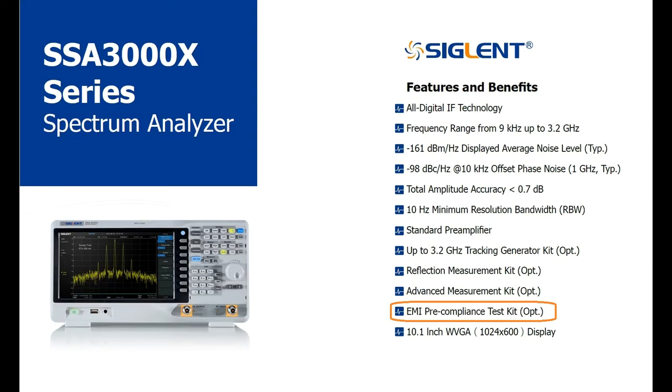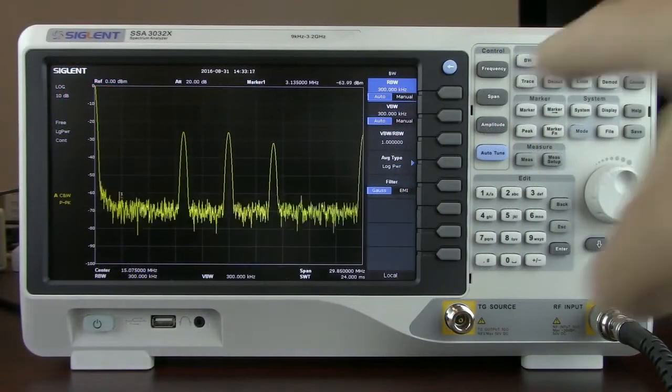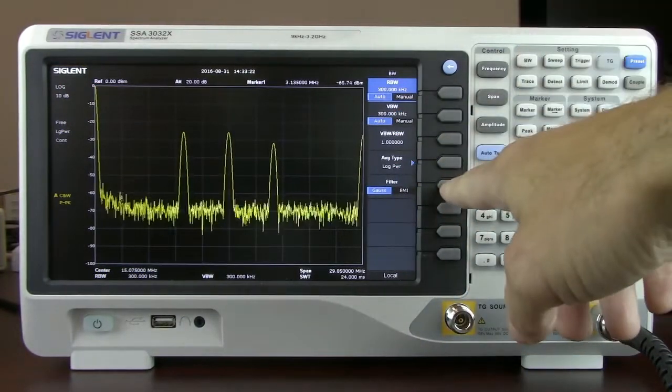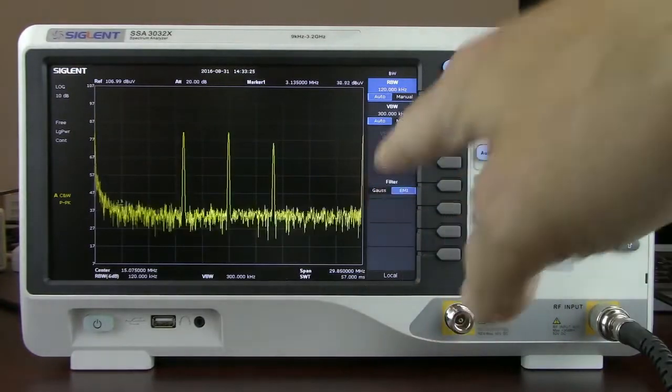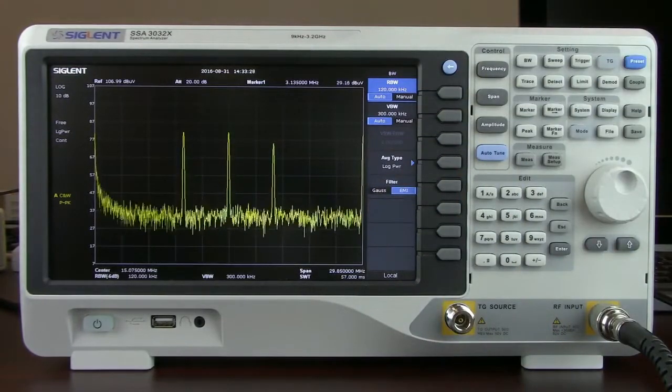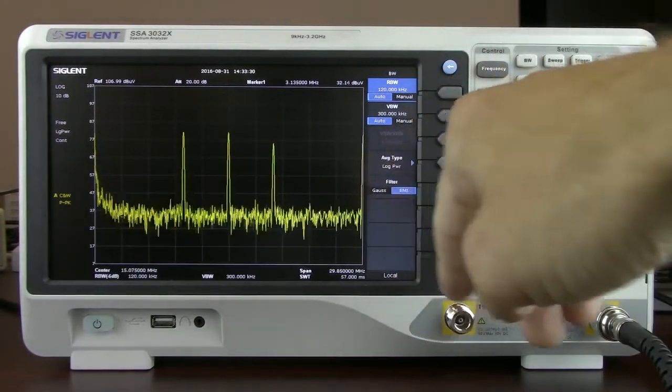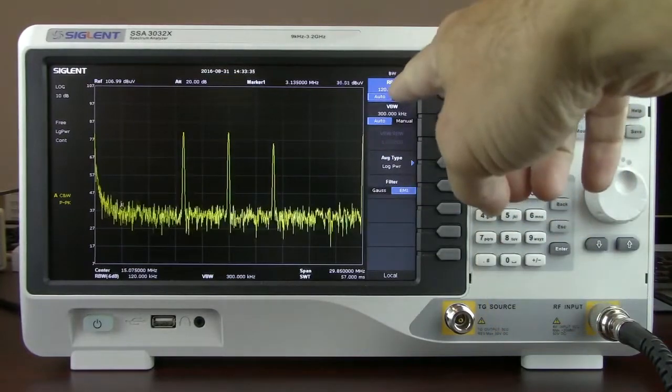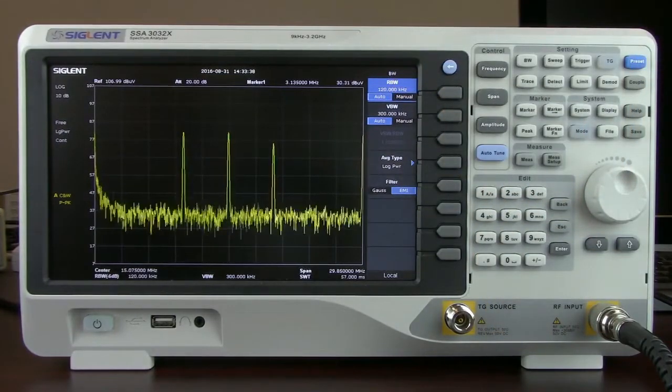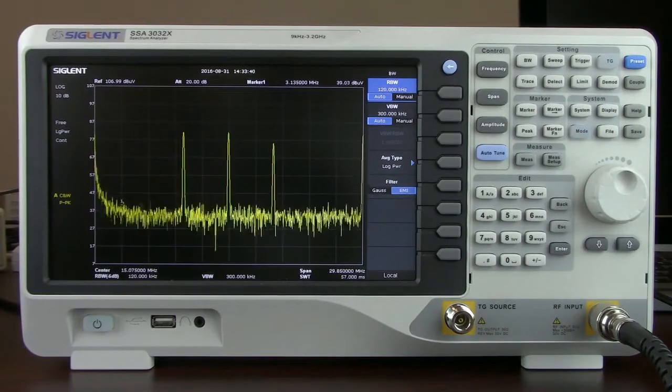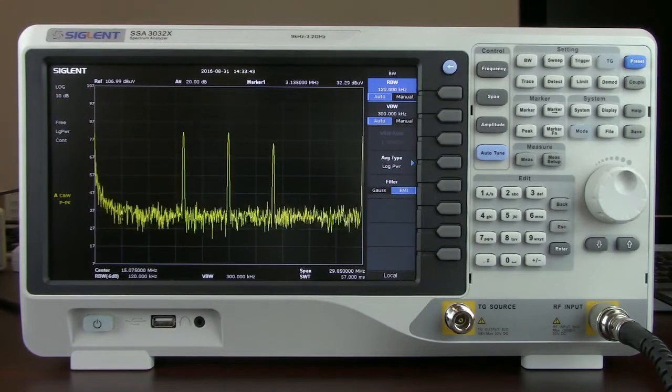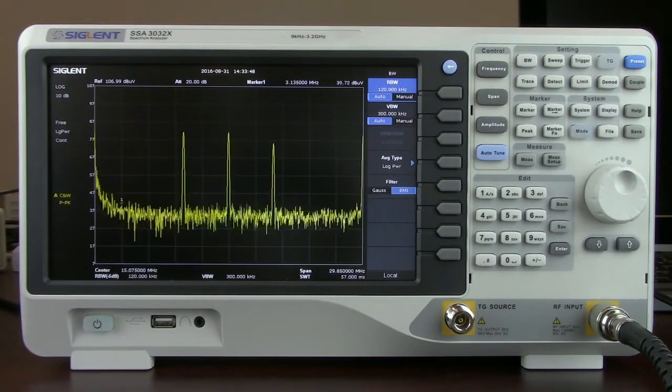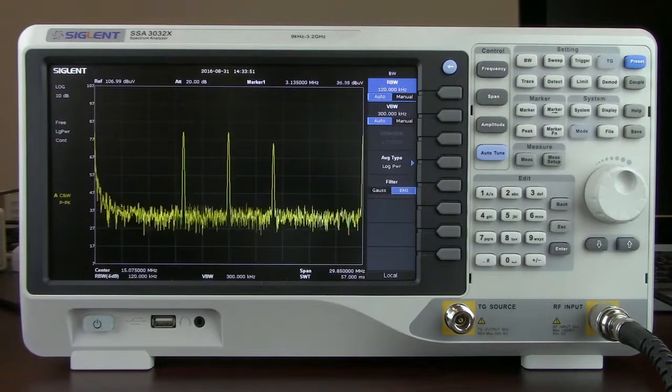Some of the things that come with this particular feature are going to be the EMI filter. We can enable that by pressing the bandwidth key and then enabling EMI. And once you've enabled the EMI filter, again that's a 6 dB filter as compared to the normal 3 dB Gaussian filter. That 6 dB EMI filter is then going to enable you to select resolution bandwidths of 200 Hz, 9 kHz, and 120 kHz.